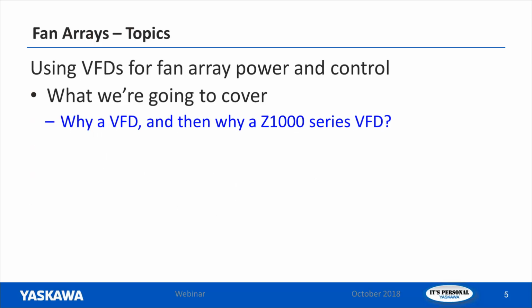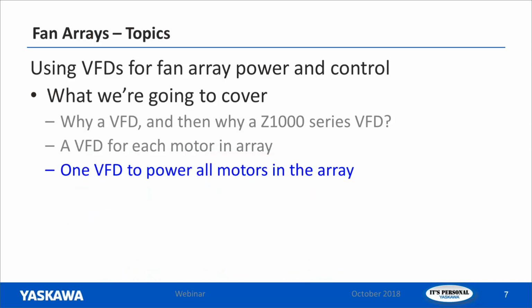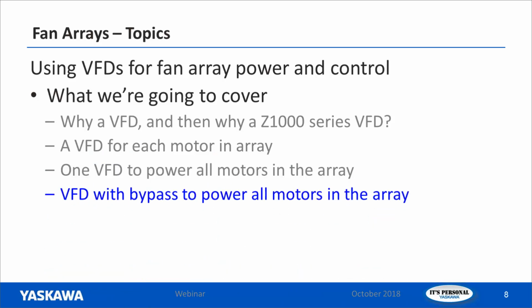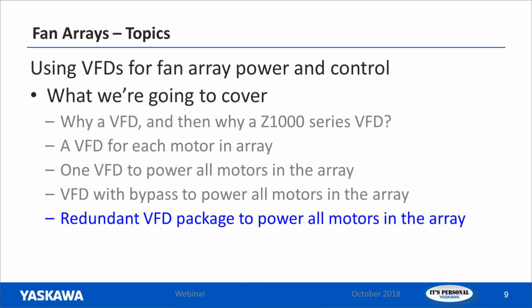So this is a brief overview of what we're going to cover and in what order. I'm going to start out with first why a VFD, and then why a Z1000 series VFD. After that, we'll move on to different configurations of using VFDs with fan arrays, and we'll start with a VFD for each motor in the array, where each motor has its own drive. Next would be using one drive to power all of the motors in the array. Next will be a VFD with bypass to power all the motors in the array, and then using a redundant VFD package to power all the motors in the array. And there'll be different reasons for using each of these.